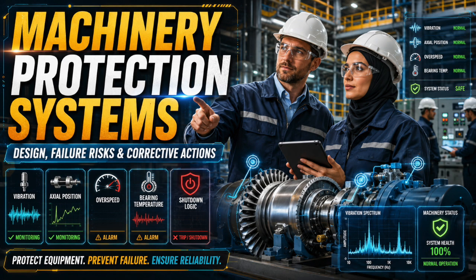A fast electronic module cannot compensate for a slow final trip path. A good overspeed design asks, how fast can the rotor accelerate? How many pulses per revolution are available? Can the sensor detect low speeds? Can passive magnetic sensors generate enough signal? Should active magnetic sensors or proximity probes be used instead?